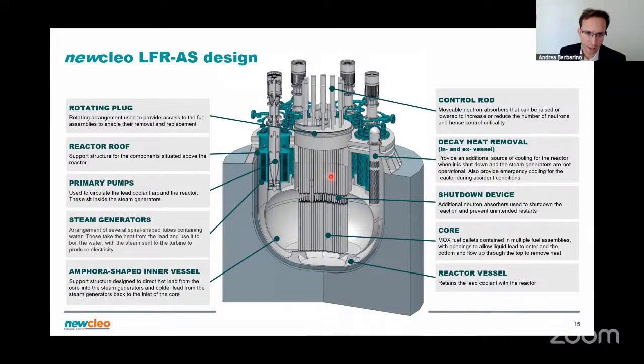In Superphénix, you have seen that there were two big components, one pumping sodium into the core and the other one extracting the heat. Well, we have condensed everything in a single component, which is the steam generator and primary pump block, which is here, which is very compact and which can also be inserted and extracted as a single component. So also from the handling point of view, it is much easier to treat than the Superphénix components. We still hang everything from above, but please check, we don't have heavy structures at the bottom of the vessel, while in Superphénix there were a bunch of structures there. We just have some features to direct lead and to avoid that the core oscillates, but no heavy structures there.